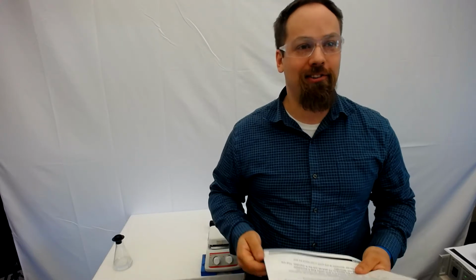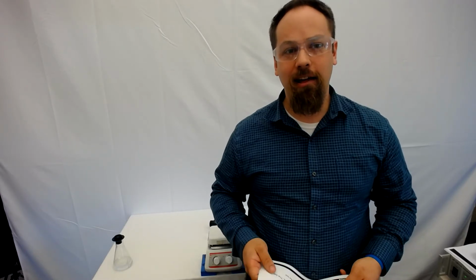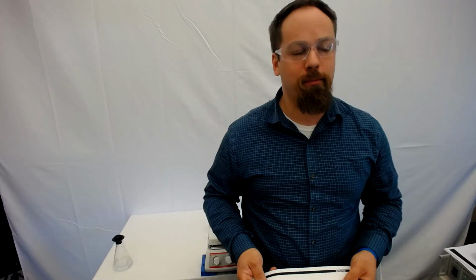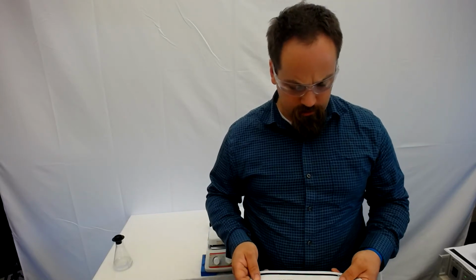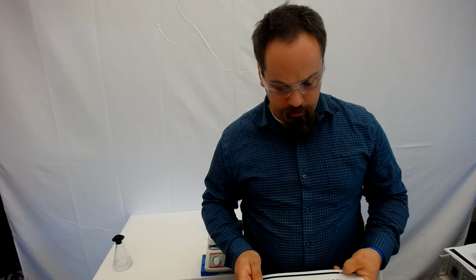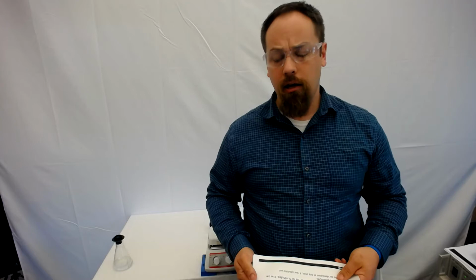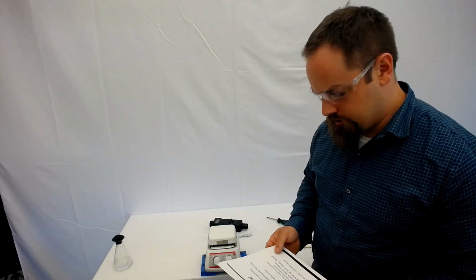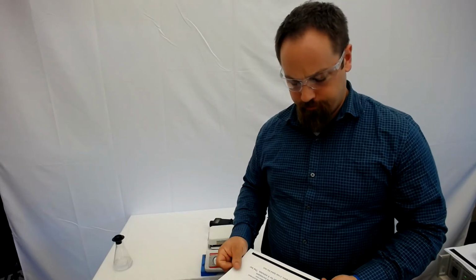Again, on this unit, very, very small changes in voltage, changes in current can impact the calibration. So it's very important that you keep using the calibration tester to give it a consistent voltage and current. So what you're looking for is at slow speed, the stir bar is turning very, very slow, and at high speed, it does not decouple. If the bar decouples at any point, it has failed the test.